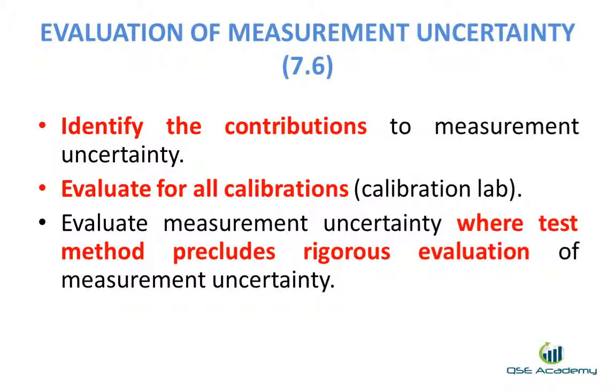7.6. Evaluation of measurement uncertainty. Laboratories shall identify the contributions to measurement uncertainty. When evaluating measurement uncertainty, all contributions that are of significance, including those arising from sampling, shall be taken into account using appropriate methods of analysis.